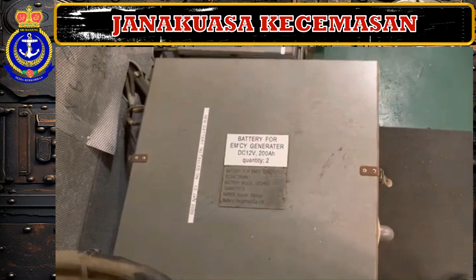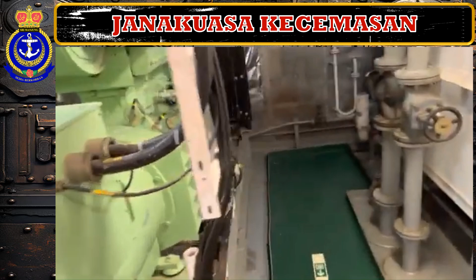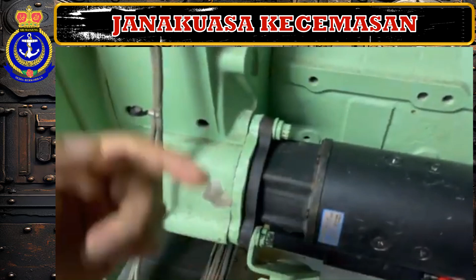These are the two batteries. This generator is designed for battery starts, 12 volt each. The two batteries we have right here will supply initial voltage to the starting motor right here. This 12 volt will come right here to the starting motor. This is the starting motor, and this is like an engaging gear. So this will energize this motor, and this has a gear which will go inside, and here is the flywheel right there. This will start engaging and it will turn the flywheel.